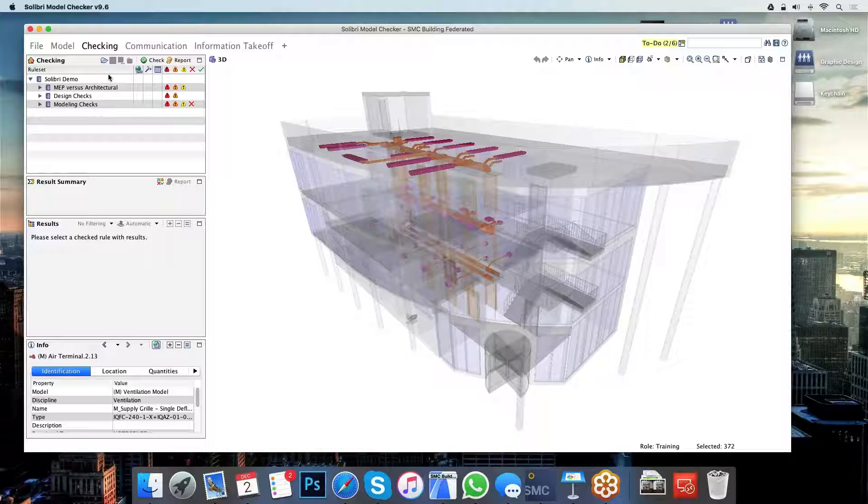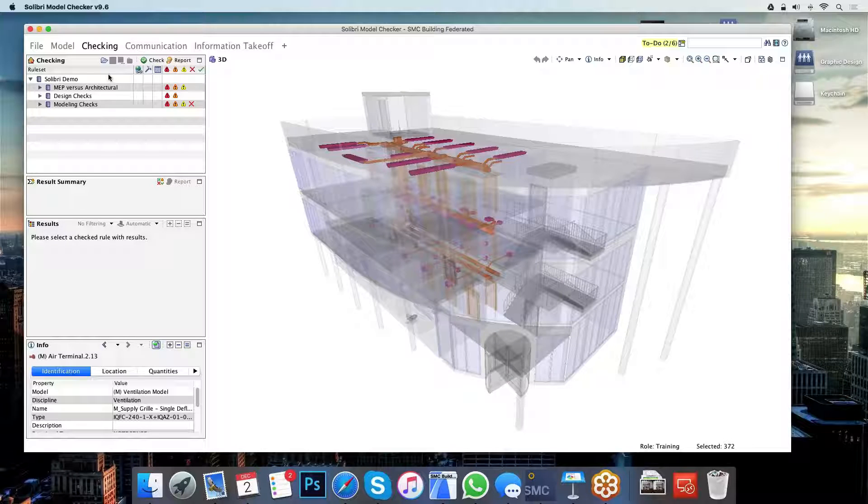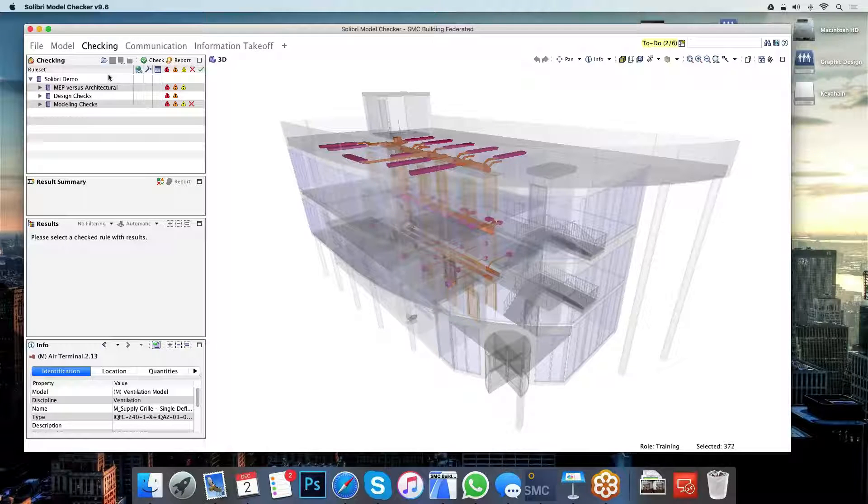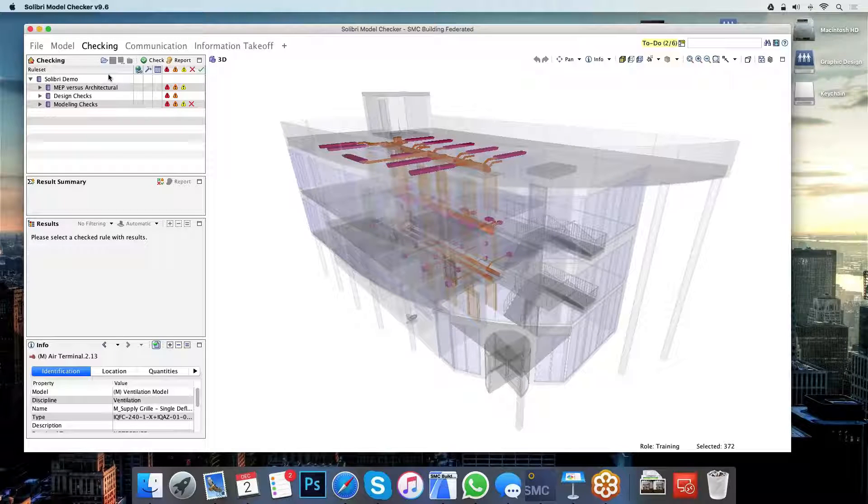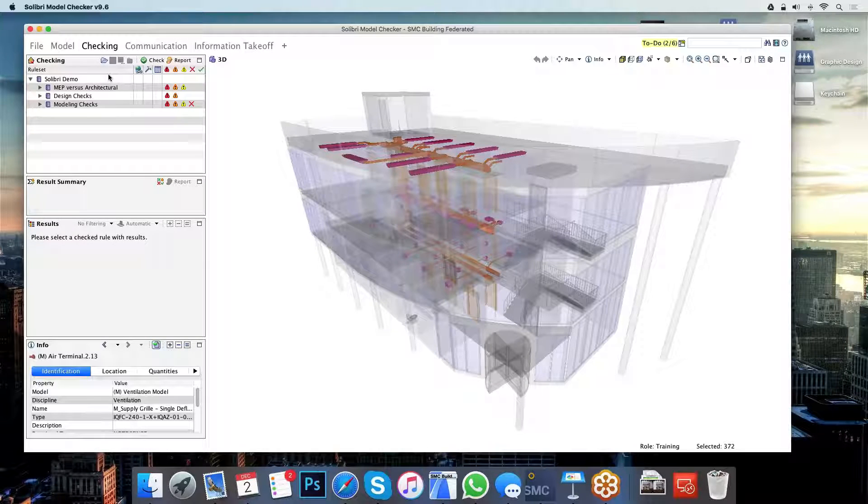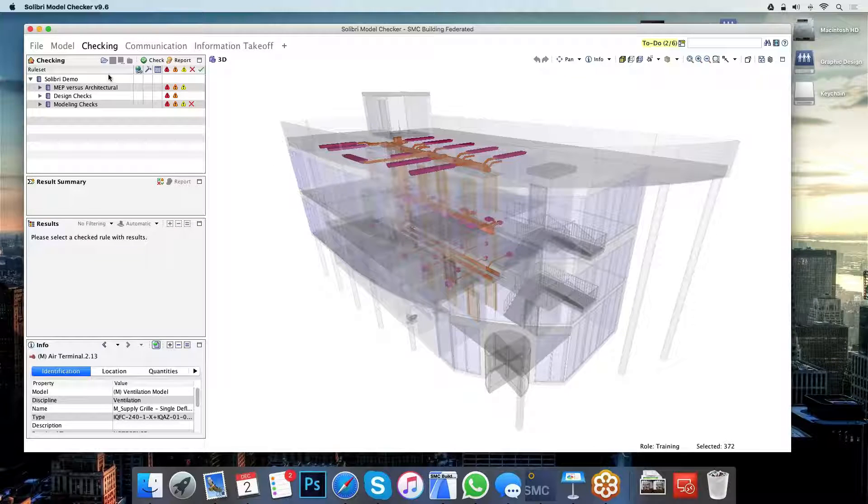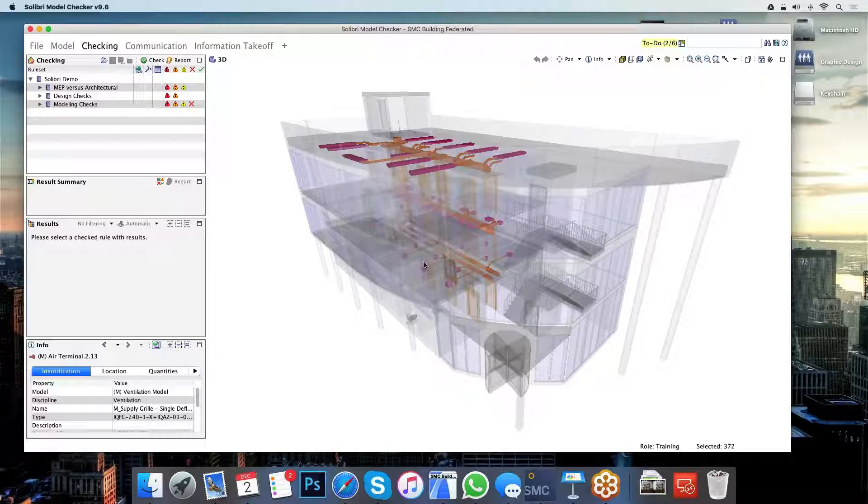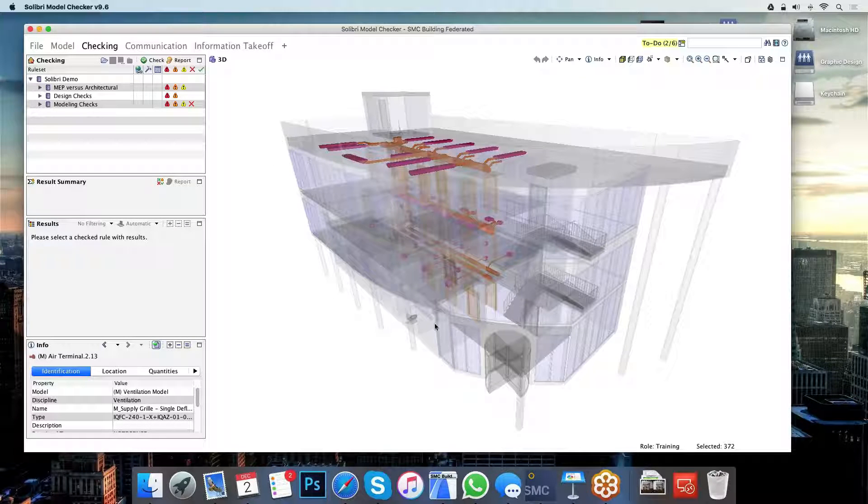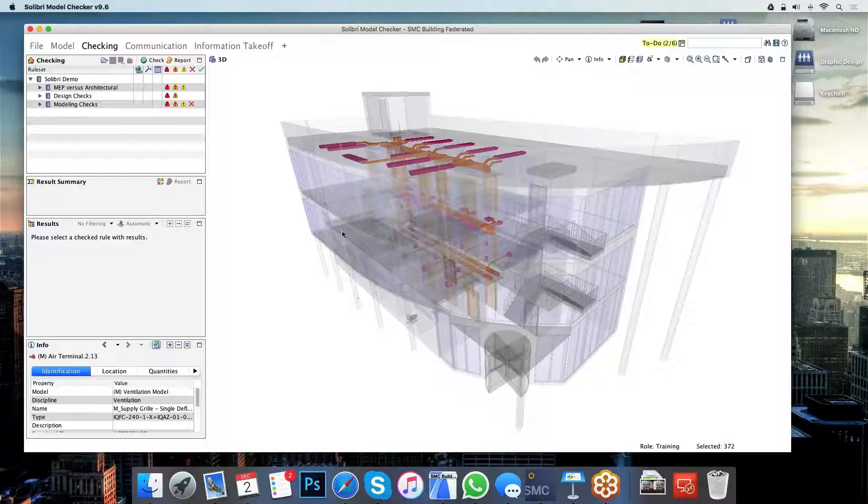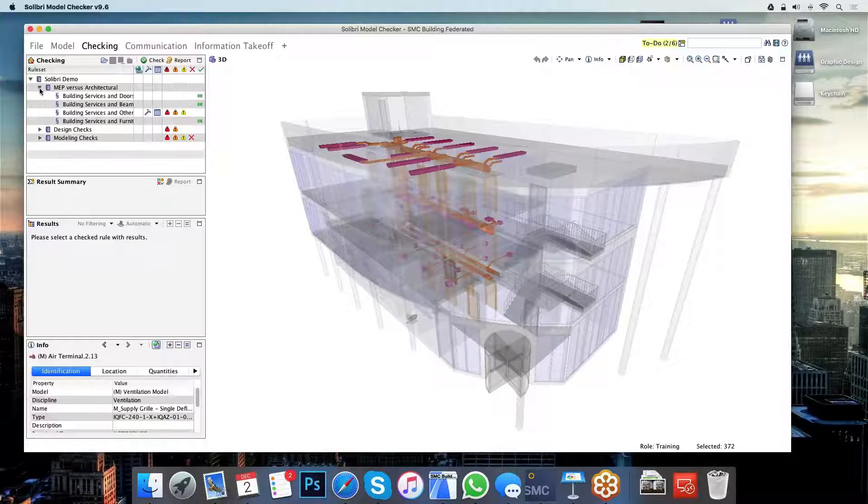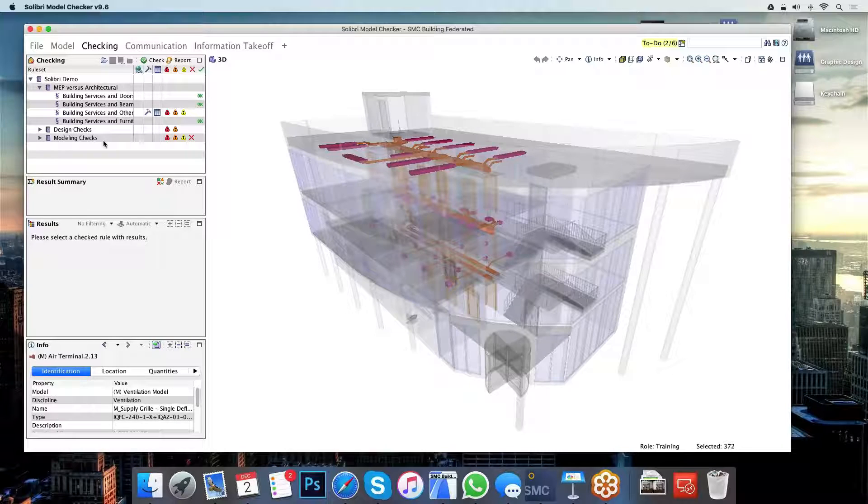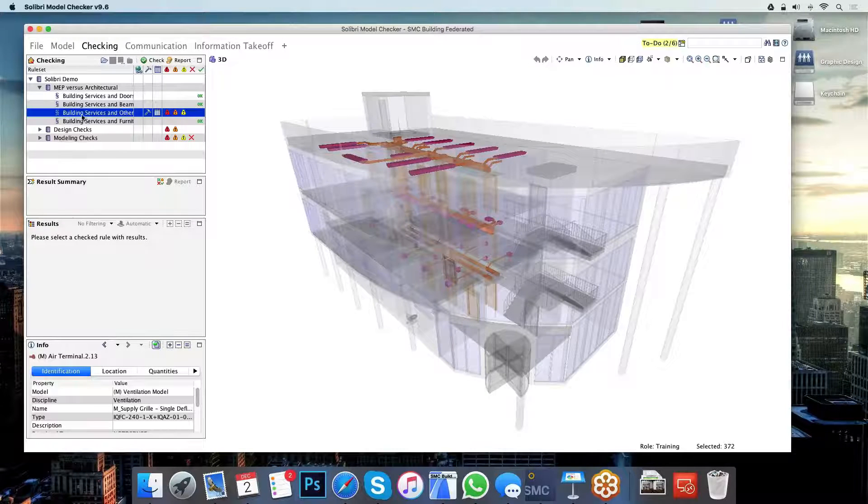Is it above half a million BTUs? It is. Well, how many exits does the space have then? Only one? Oh, this will be an issue. You actually need two. So we can perform these automated checks on the building model. And Solibri will come back to us with these answers, highlighting the issues that we might have created in the design process. So let's actually take a look at some of these issues that Solibri has highlighted for us today.